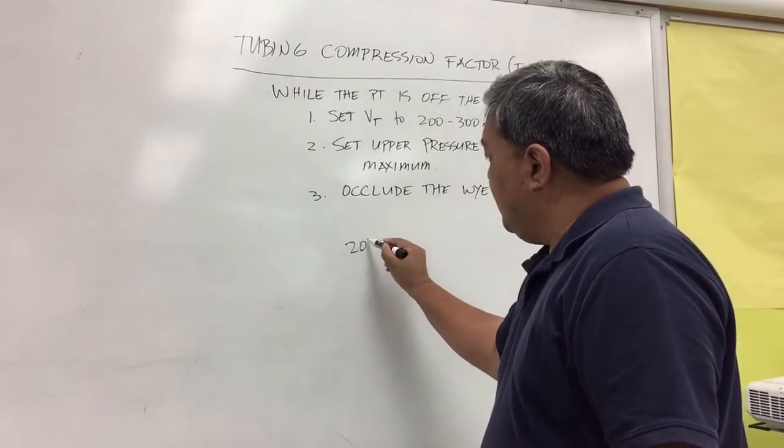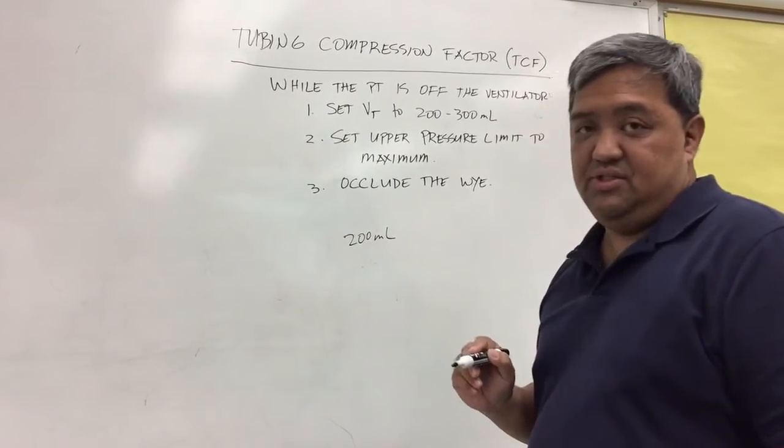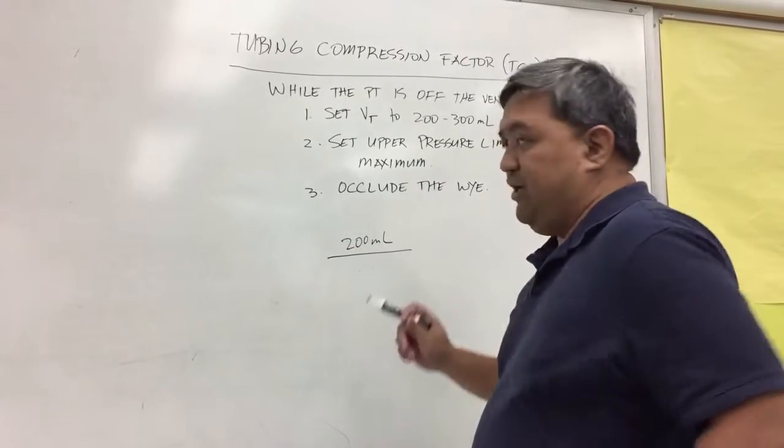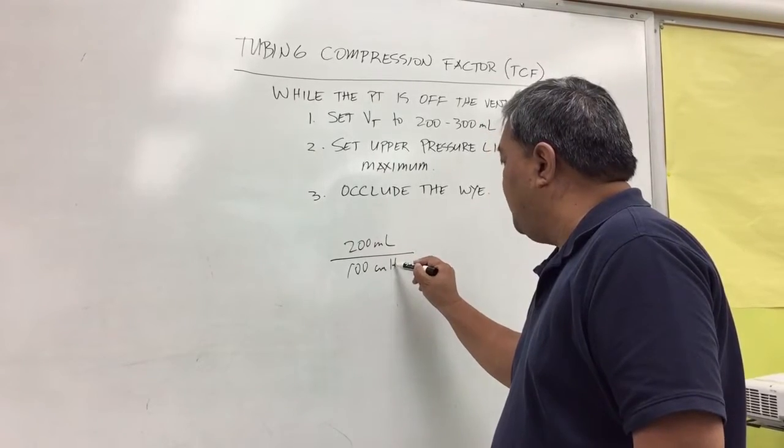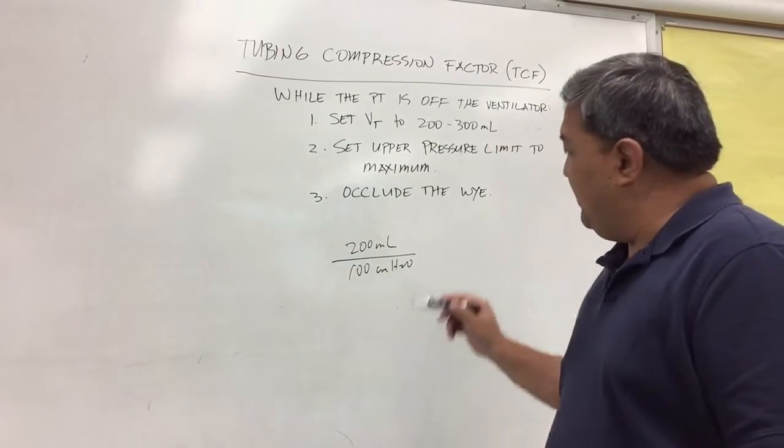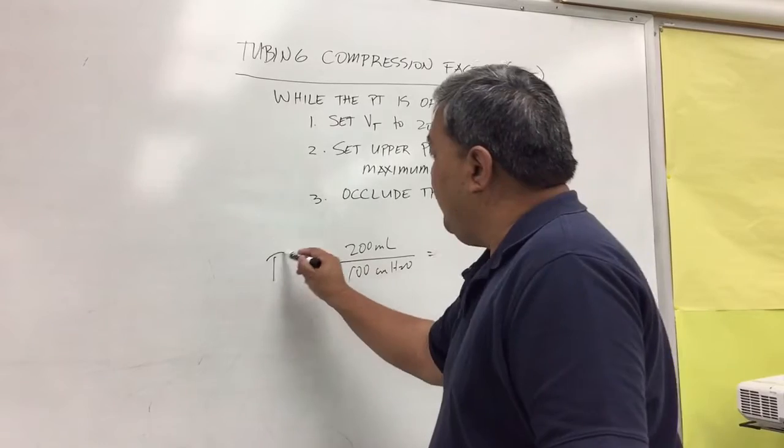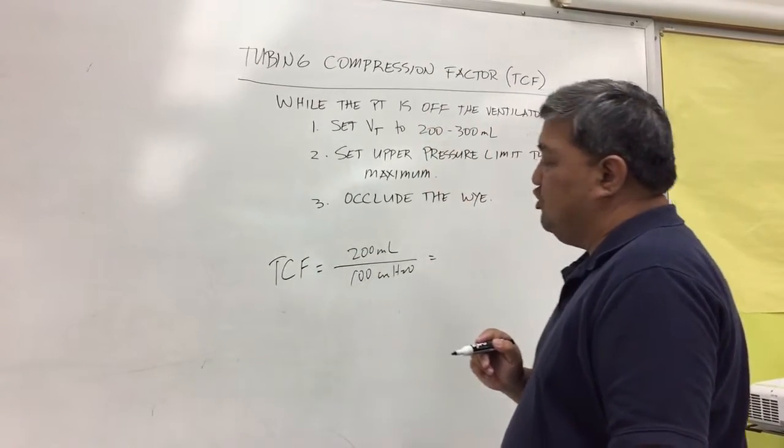Once you occlude the Y, you will generate a certain pressure. So let's say you set your volume at 200 mls, and the pressure generated because you occlude the Y is about 100 centimeters of water pressure. Based on this, you will now have a tubing compressibility factor of 2 mls per centimeter of water pressure.